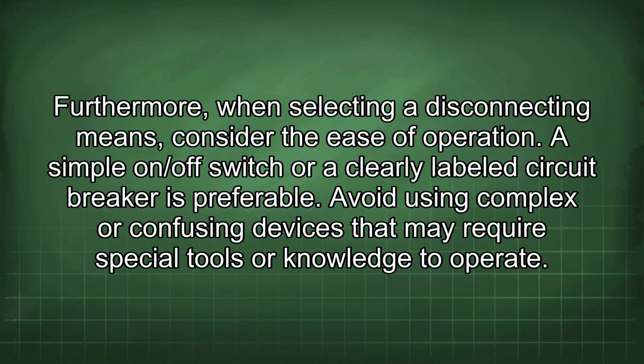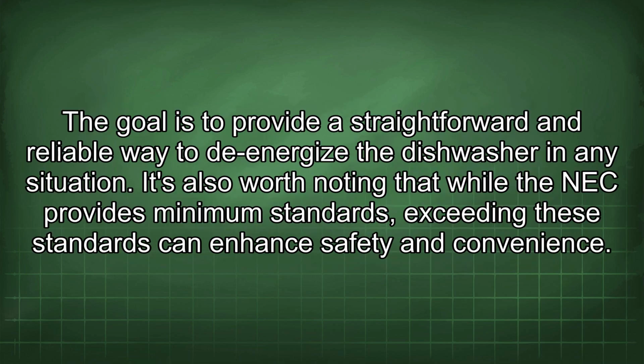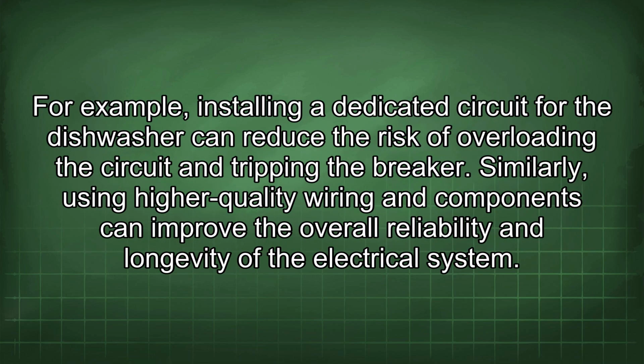Furthermore, when selecting a disconnecting means, consider the ease of operation. A simple on/off switch or a clearly labeled circuit breaker is preferable. Avoid using complex or confusing devices that may require special tools or knowledge to operate. The goal is to provide a straightforward and reliable way to de-energize the dishwasher in any situation. It's also worth noting that while the NEC provides minimum standards, exceeding these standards can enhance safety and convenience. For example, installing a dedicated circuit for the dishwasher can reduce the risk of overloading the circuit and tripping the breaker. Similarly, using higher quality wiring and components can improve the overall reliability and longevity of the electrical system.